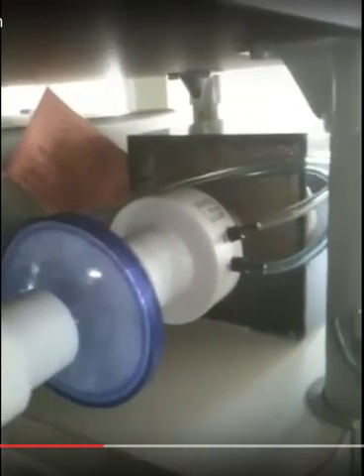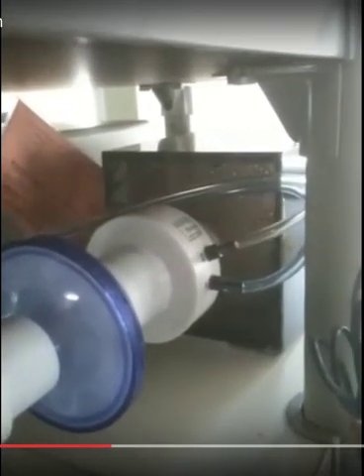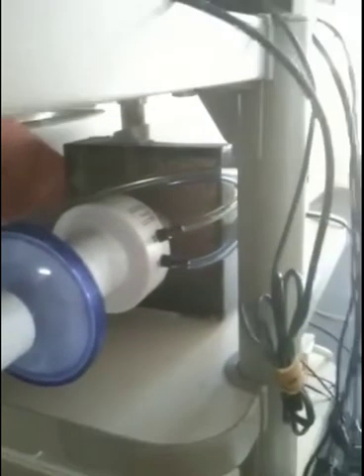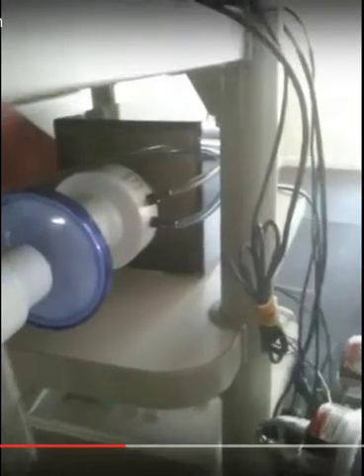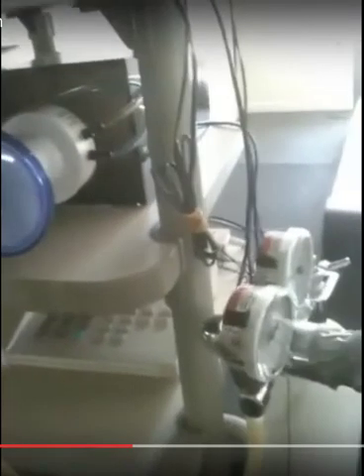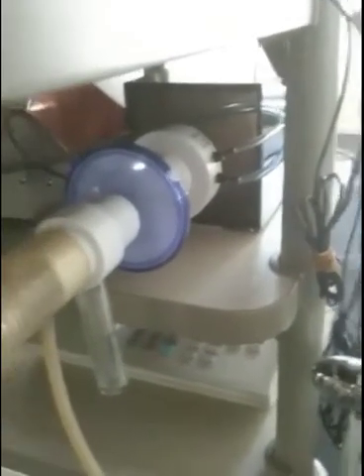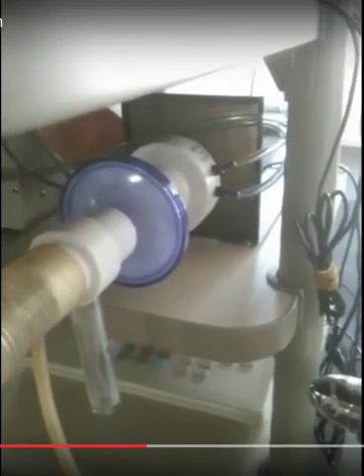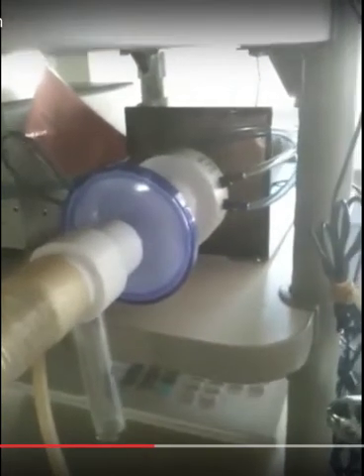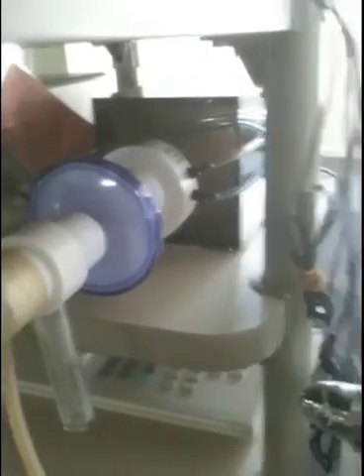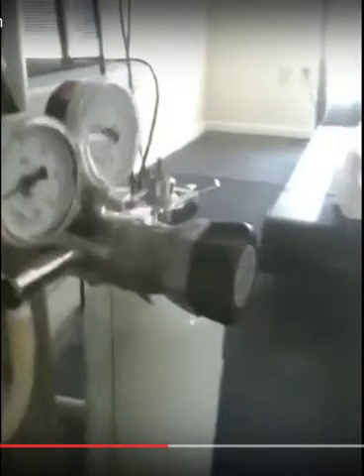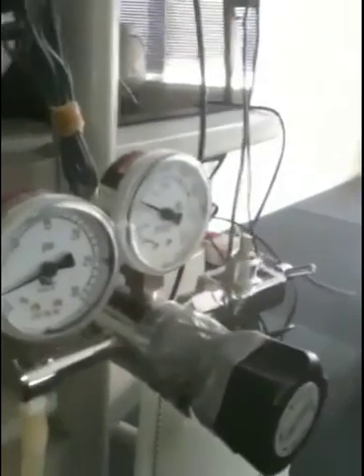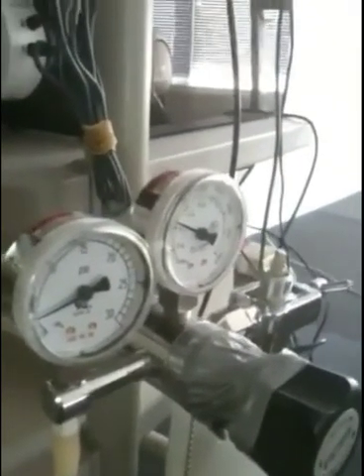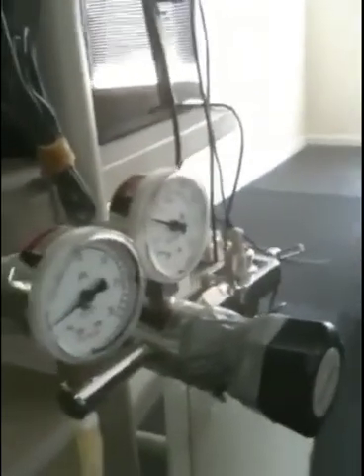So if I know the amount of oxygen that's in the air, and I know how much air the client is breathing in, and I know the difference between the oxygen that's in the air and the expired air of the client, the difference represents what's being utilized in terms of oxygen and what's being produced in terms of carbon dioxide. Okay, and then the gas tank over here is used to calibrate the oxygen analyzers and the carbon dioxide analyzers.